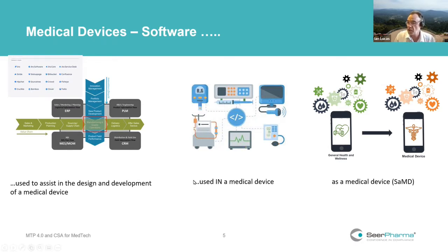Within medical devices, we actually have software within a medical device, and these days we have software as a medical device. We all know what software in a medical device is, and probably most of you know what software as a medical device is as well. It's those apps and programs that are not implicitly involved with a medical device, but take data, whether from the device or from your own body, and then use that to make decisions that then drive you to go back and use the medical device in a certain way.